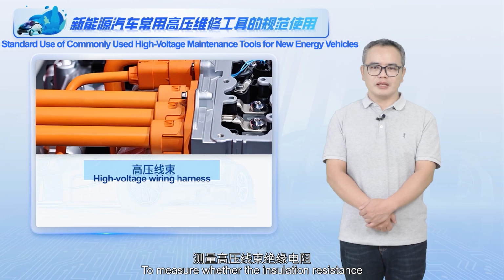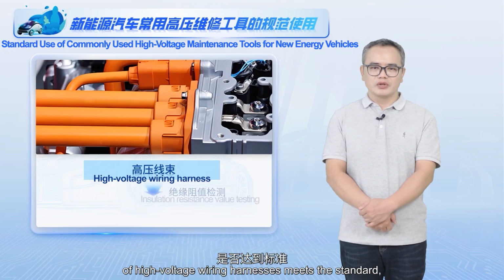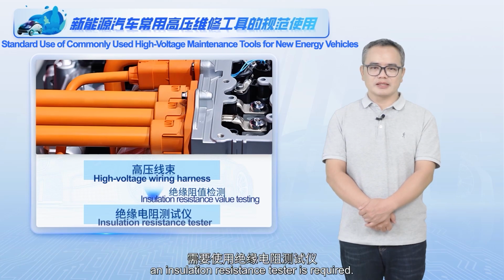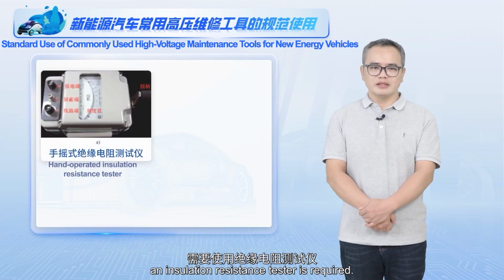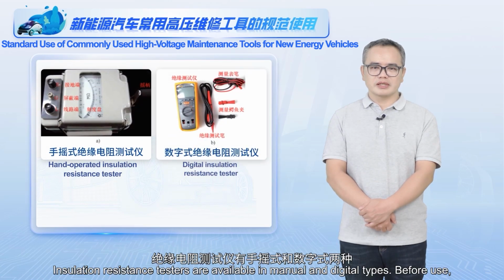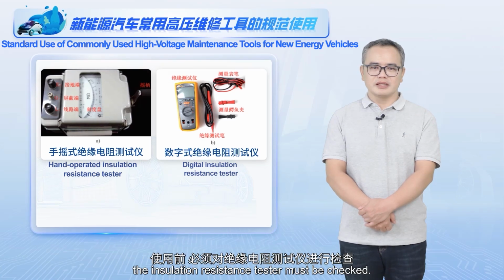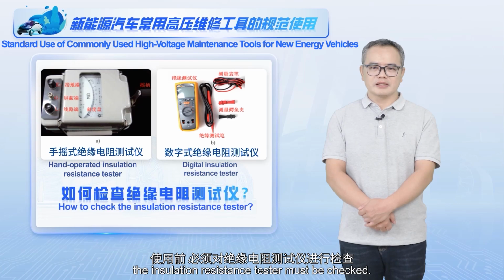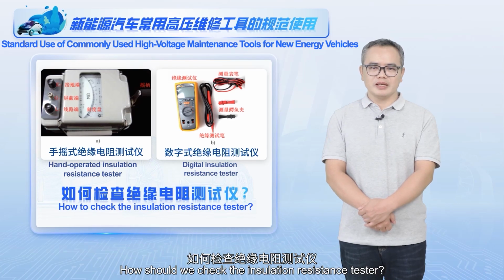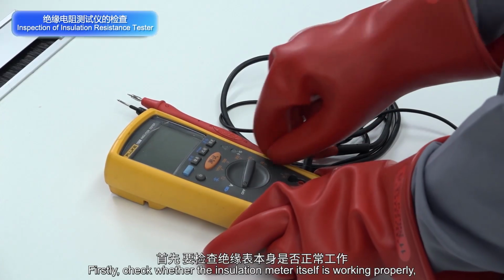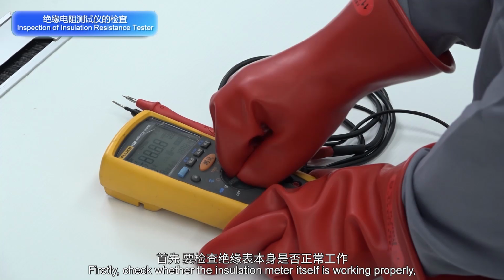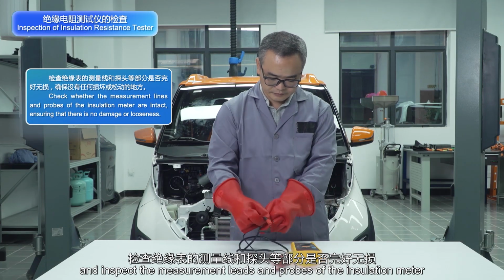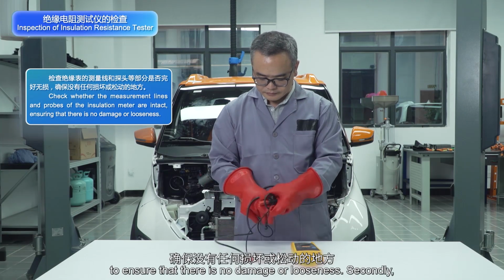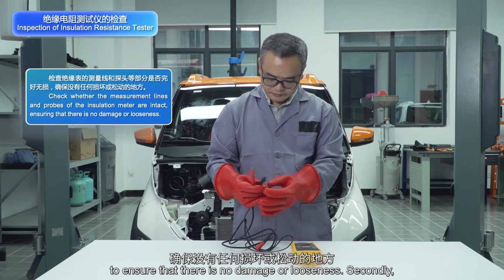To measure whether the insulation resistance of high-voltage wiring harnesses meets the standard, an insulation resistance tester is required. Insulation resistance testers are available in manual and digital types. Before use, the insulation resistance tester must be checked. How should we check the insulation resistance tester? Firstly, check whether the insulation meter itself is working properly, and inspect the measurement leads and probes of the insulation meter to ensure that there is no damage or looseness.